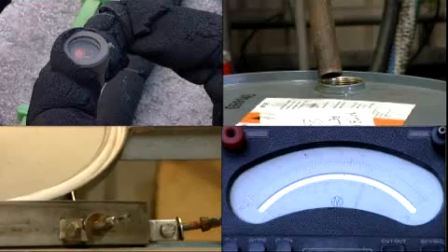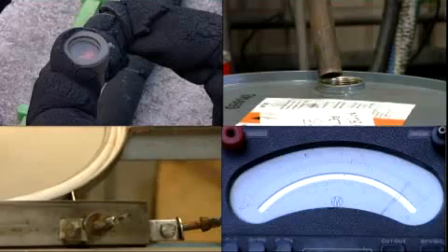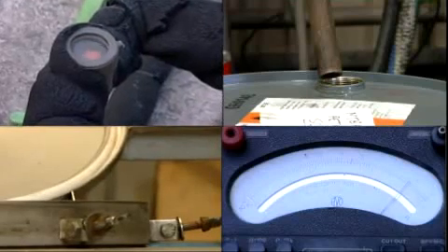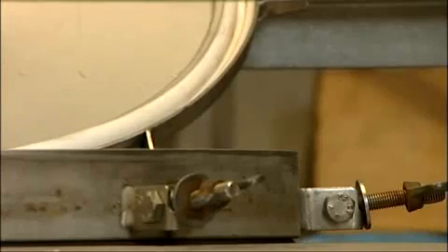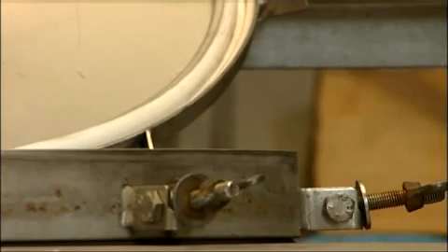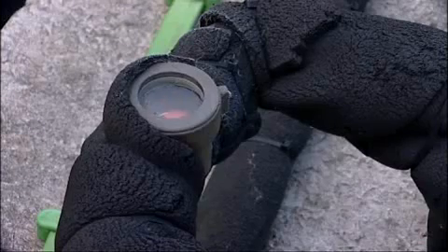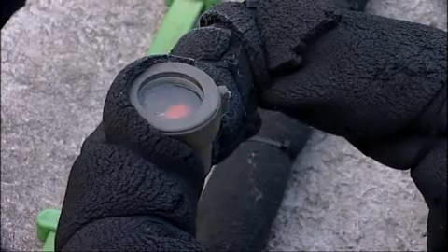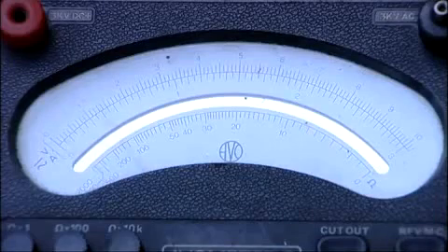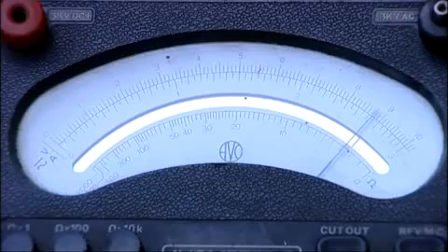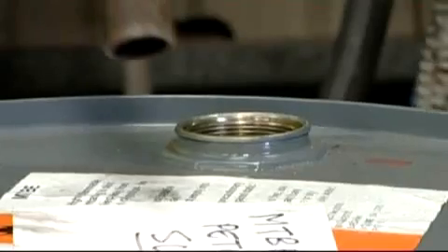Certain conditions need to be met before an electrostatic discharge can cause ignition. The mixture of the solvent vapor and air must be within its explosive range and be present. There must be means of generating the electrostatic charge, and the charge must accumulate to a level with enough energy to initiate an igniting spark.